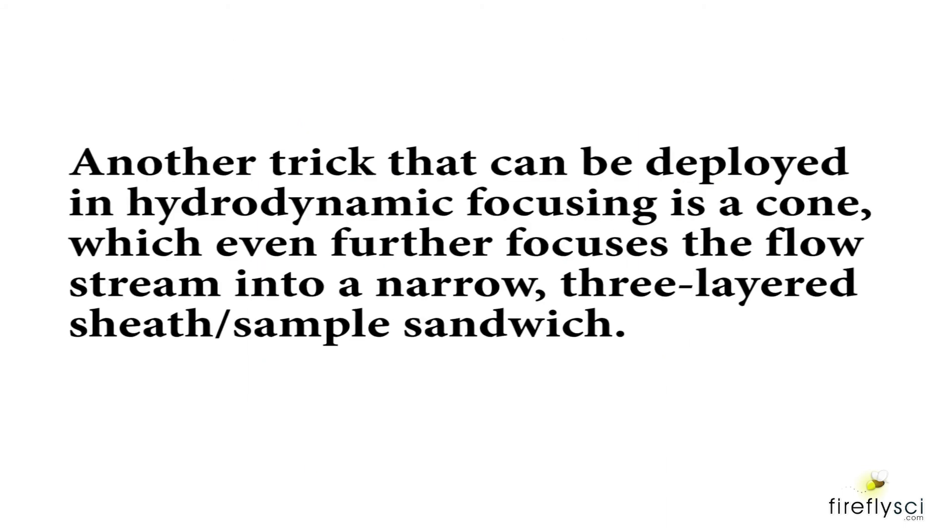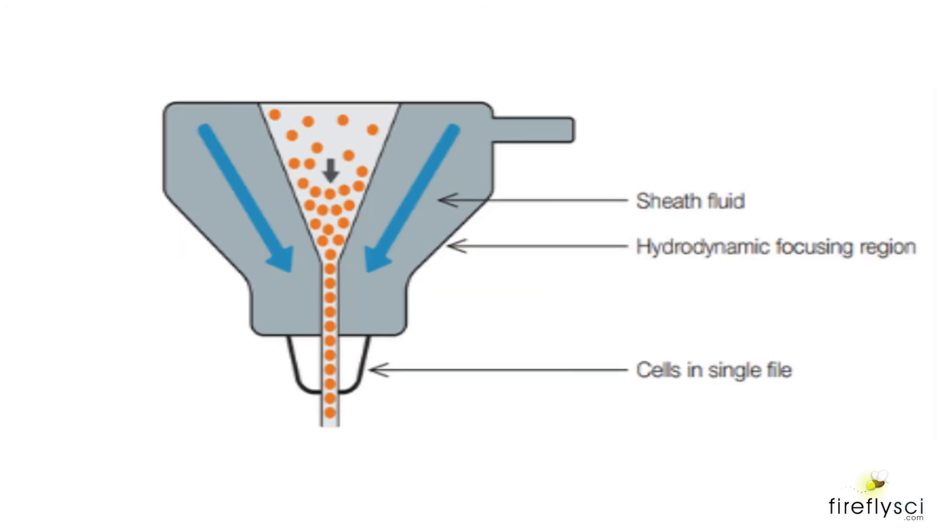Another trick that can be deployed in hydrodynamic focusing is a cone, which even further focuses the flow stream into a narrow, three-layered sheath-slash-sample sandwich. By manipulating the flow rates of the sheath, the core sample stream can be even further focused through the flow channel. It's important that the cone not have rough ridges in order that it can reduce any turbulence that might disturb the sheath layers or core stream.